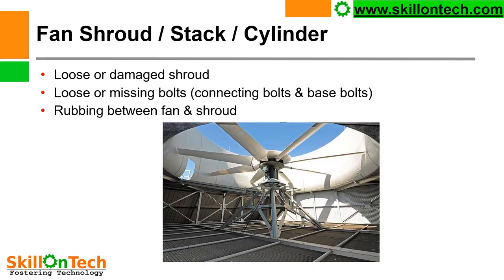Fan shroud, stack, or cylinder — you can see a picture of a fan cylinder and a fan with a gear box. Common problems include loose or damaged shrouds, loose or missing connecting bolts and base bolts, and rubbing between fan and shroud. If your fan is rubbing with the inside periphery of the fan cylinder, it will make noise and can damage the fan cylinder and blades. Connecting bolts and base bolts may loosen during operation; they shall be tightened or replaced.